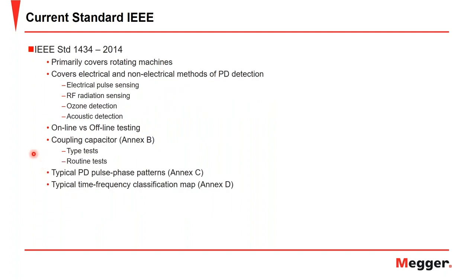Here we have the current IEEE standard, IEEE 1434. This primarily covers rotating machines, but also covers the electrical and non-electrical methods of PD detection, such as electrical pulse sensing, RF radiation sensing, ozone detection, and acoustic detection. It has good coverage of online versus offline testing, and also covers the coupling capacitor within Annex B, covering type tests and routine tests. There are some neat typical PD pulse phase or PRPD patterns that can be seen in Annex C, as well as typical time frequency classification maps seen in Annex D.